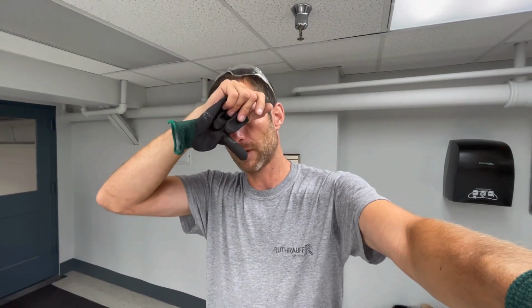So I'm trying to remember, is that belt driven? It's been so long since I had to work on that. Could be a loose belt. It could be a bad set of bearings. It could be a squirrel cage out of balance. Could be a bolt or something that held onto the bracket, could be broke, and it's throwing it off balance and shaking everything. But it's not going to fix itself, people. So let's take a look.